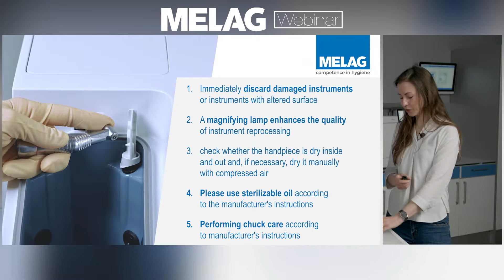And as we mentioned, point number 5 would be the chuck care. Perform a chuck care. We generally recommend doing it at least once a week, but if the manufacturer says it's necessary more often, then of course, please follow, check out the instructions of the manufacturers. Very, very important. Yes, in regards to oiling, of course, the manual solution may be shown on the screen here, and like I mentioned before, later on we will also show you how to do it with our new adapter in the MELAG here. Wonderful. Okay, next step in our hygienic cycle workflow for handpieces mainly. Now we're coming to the steam sterilization part.